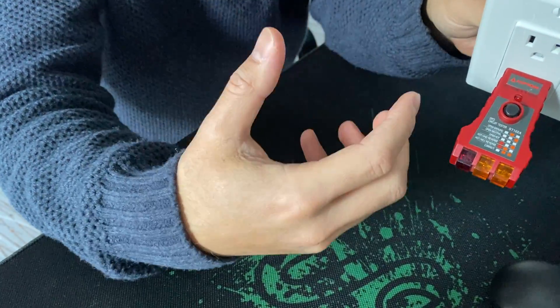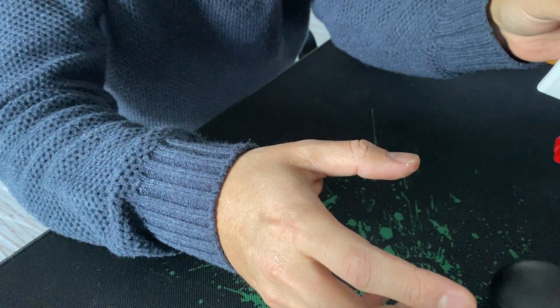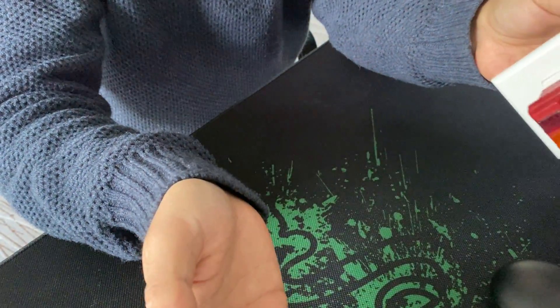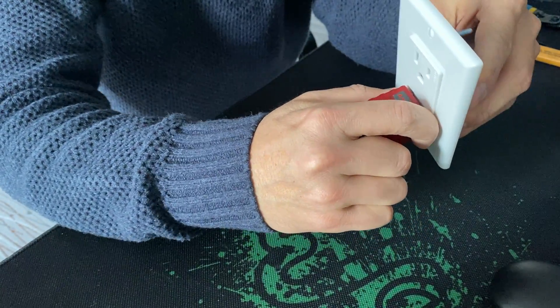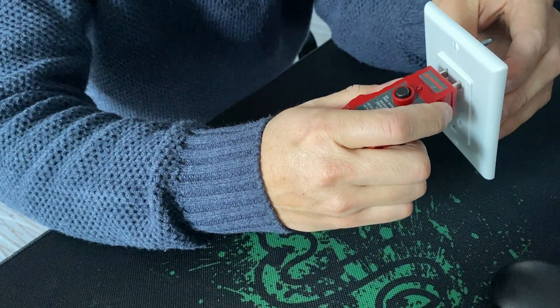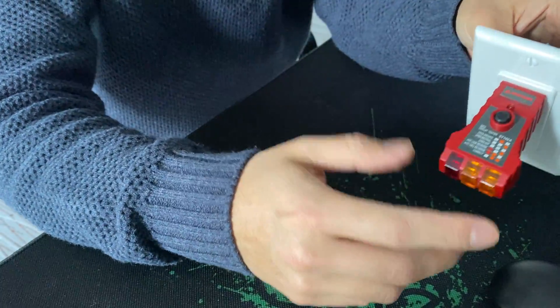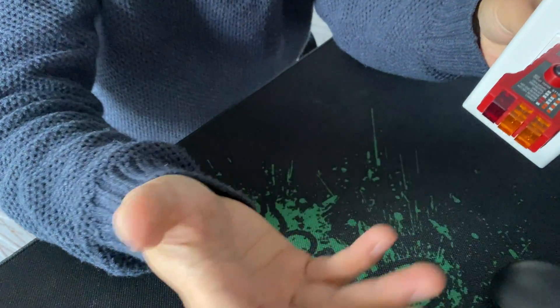In my experience working as an electrician for the past three to four years, I've come across this many times — even in brand new homes that just finished inspection. After people started loading the outlets, they just stopped working or had a loose connection. In many cases it was basically one loose wire.